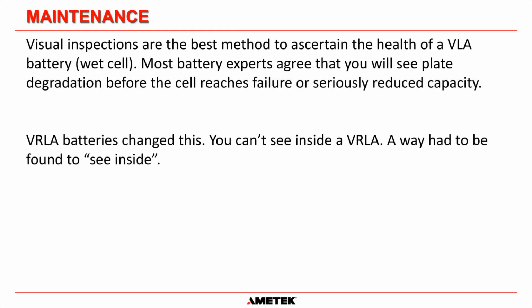So historically, visual inspections are the best method to ascertain the health of a vented lead acid battery. In other words, a wet cell, where you can see the electrolyte inside the battery. Near enough all battery experts agree that you will see plate degradation. You will see the plate start to fail before the cell reaches failure or seriously reduced capacity. So by doing a visual inspection on a regular basis on wet cell batteries where you can see inside the battery, that is the best way to perform your inspections.